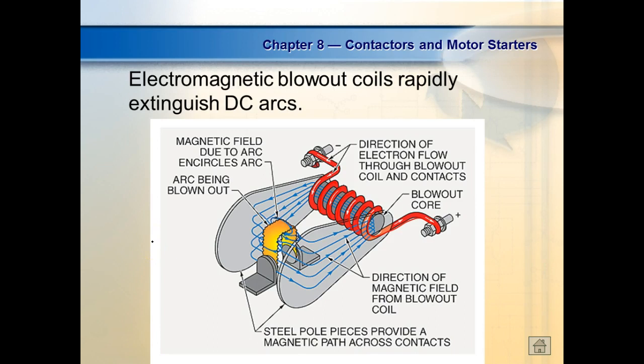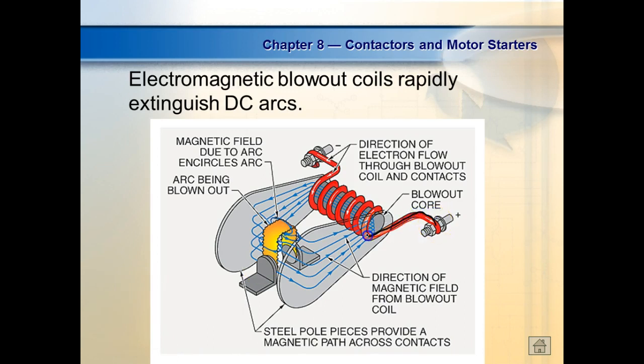So on these big DC power relays, we have what we call a blowout coil. And the blowout coil has a coil, and anytime I put current through the coil, it generates a magnetic field. Everybody okay? Does that make sense? And then the load actually runs through this coil right here. So the motor would run through this. Now it's going to drop a little bit of voltage, but it's not going to be enough voltage to affect the running of the motor, right? You understand that? And of course, what happens, the contacts are closed. They don't show you that. Now what happens is, I wish I had that set up. We got a setup over there where we have a coil of wire.